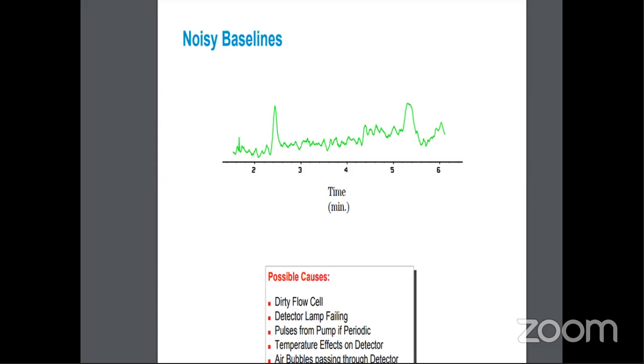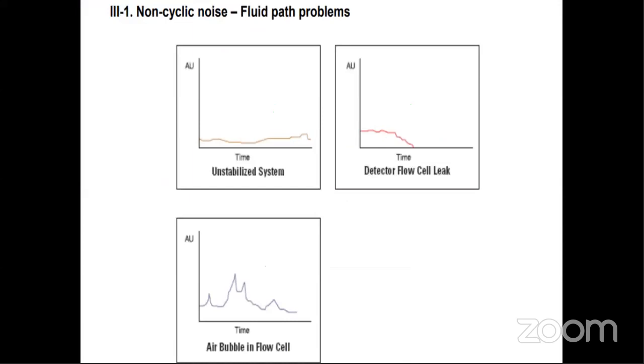Or the problem may be that an air bubble is passing through the detector, which I think we have discussed in depth before this slide. So there are again three chromatograms reflecting the same concept. An unstabilized system because of the pump or the column or the injector. Then a detector flow cell leak. You can easily identify that there is no flow, and there is a cell leakage, so you won't find any detection. And in the last slide, we can see a lot of noisy or wavy nature appearing in the detection. It means there is some air entrapment in the detector itself.